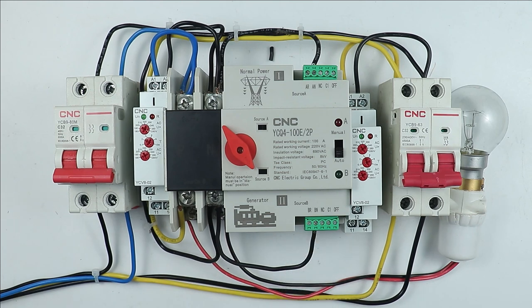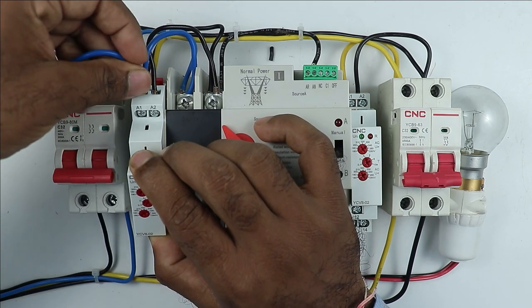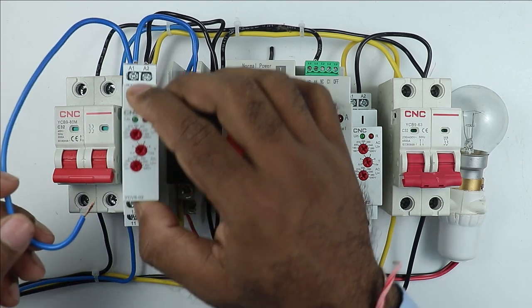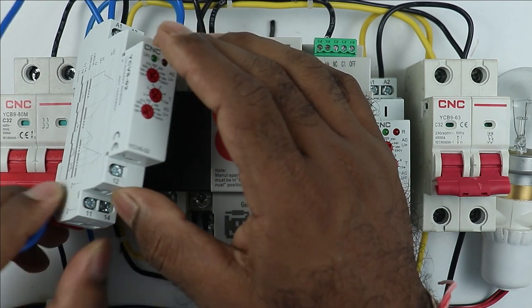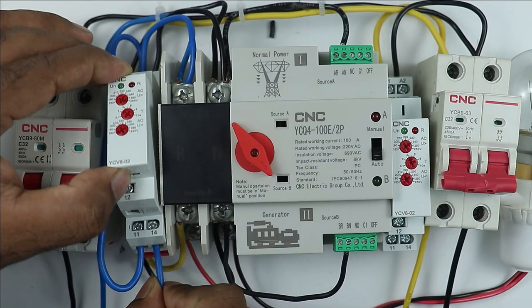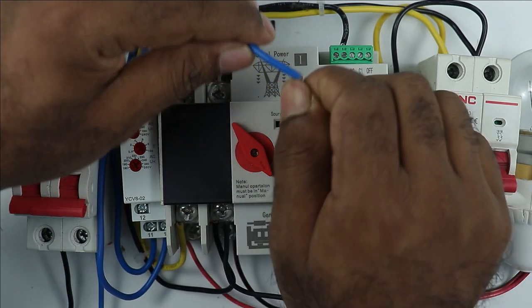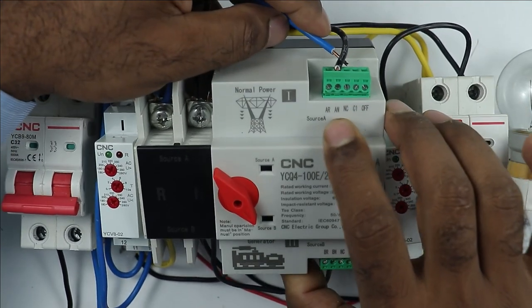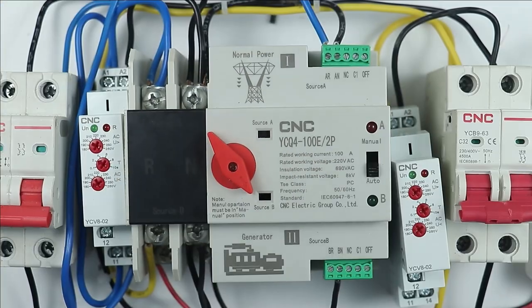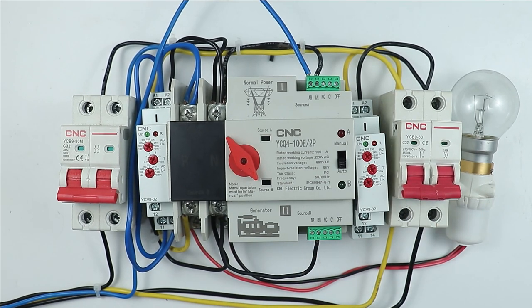To make sure this happens, connect one more wire at the A1 terminal of this relay — this wire will carry the phase supply. Take the other end of this wire and connect it to the 11 number terminal, which is the common terminal, of this relay. The 14 number terminal of this relay is the normally open (NO) contact. Connect one wire at the NO contact and take its other end to the control terminal of the normal power supply on the ATS — that is, the AR terminal, which is the phase terminal of source A. This way, power is supplied to the ATS control terminal through the relay output.